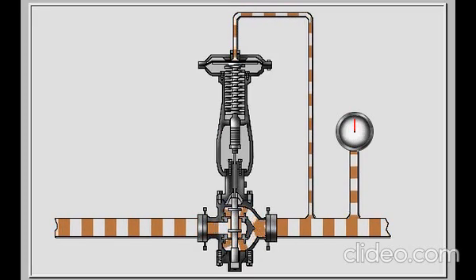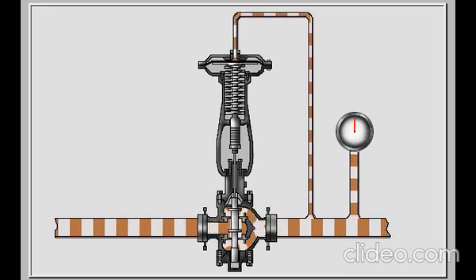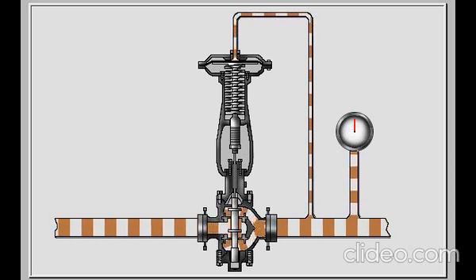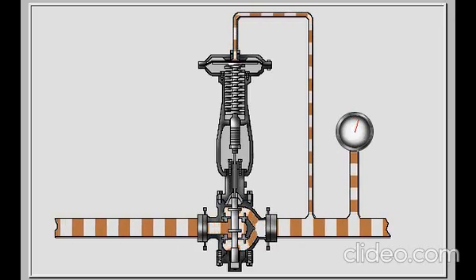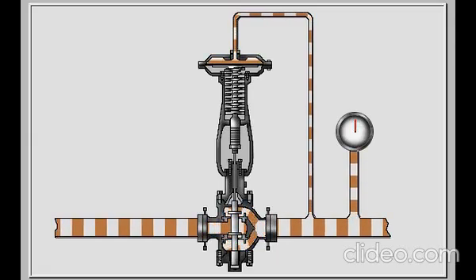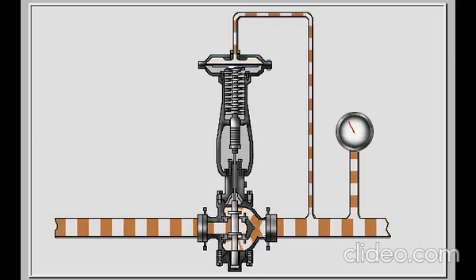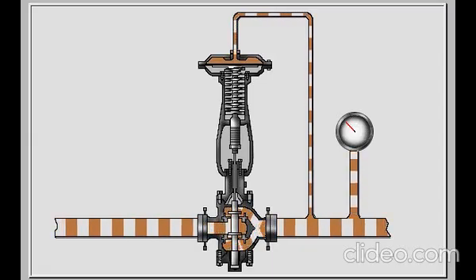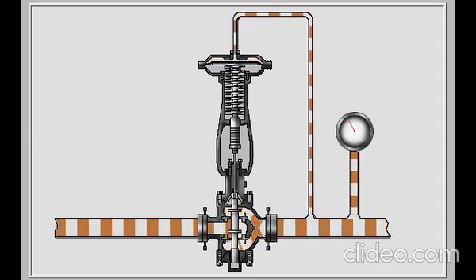The top side of the diaphragm inside VPR 2-1 is connected to the bearing header downstream of the regulator valve. The bottom side of the diaphragm is connected to the actuator spring. If lube oil pressure in the bearing header increases, the diaphragm will be forced downward, lowering the valve plug until the bearing header pressure is reduced to 26 PSI. If lube oil pressure decreases, the diaphragm will be forced upward by the actuator spring, raising the valve plug until the bearing header pressure is restored to 26 PSI.